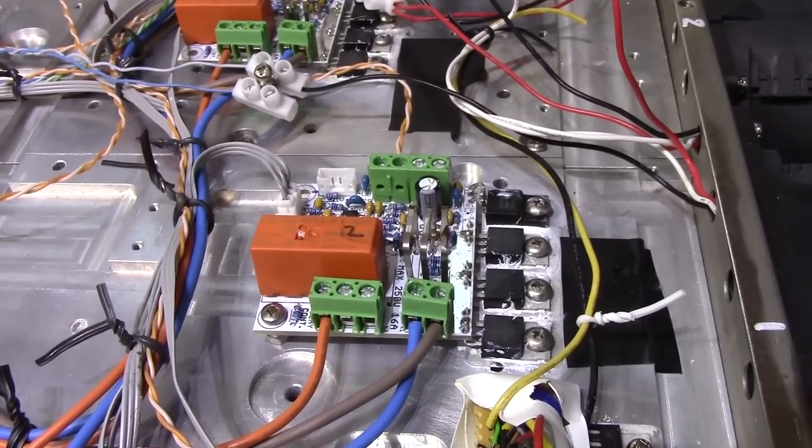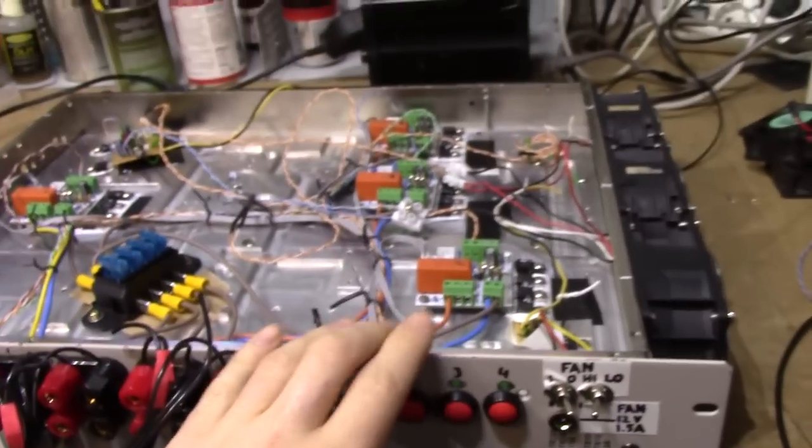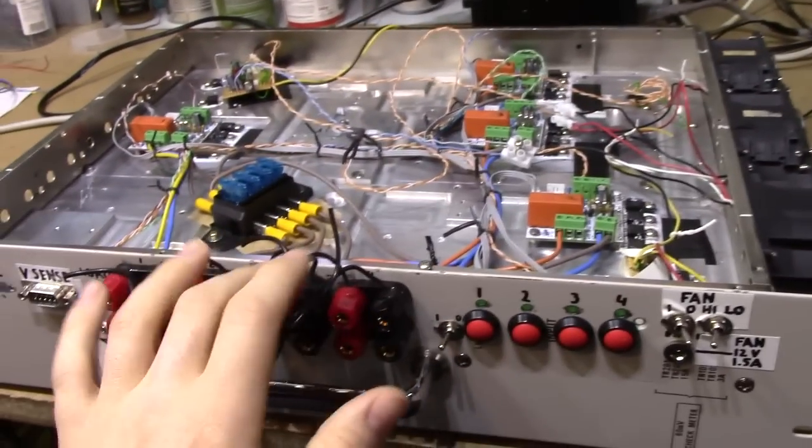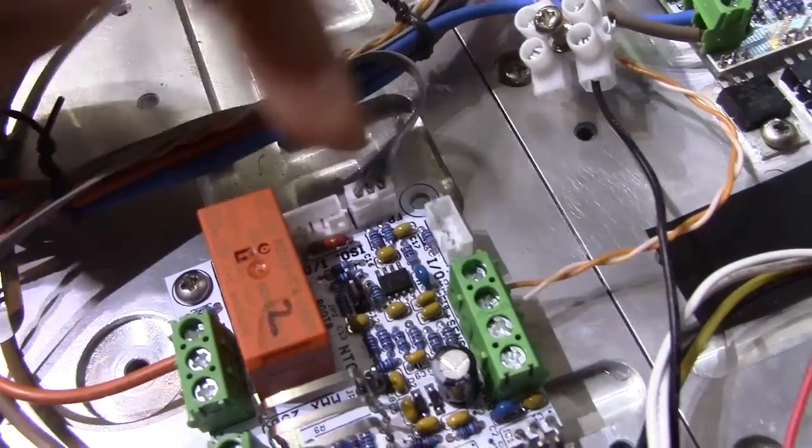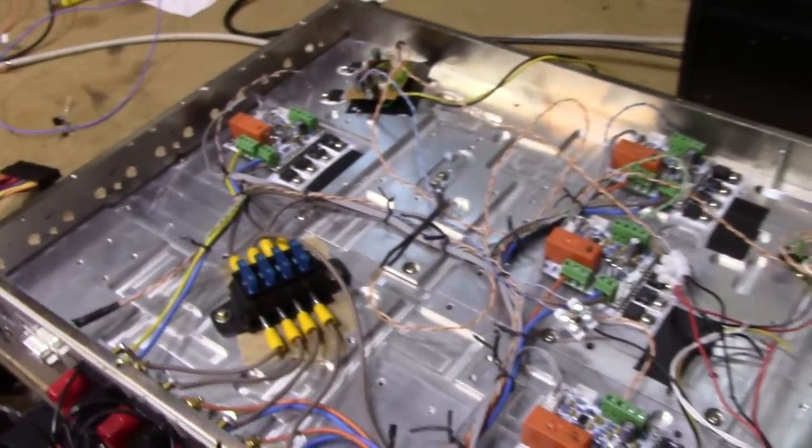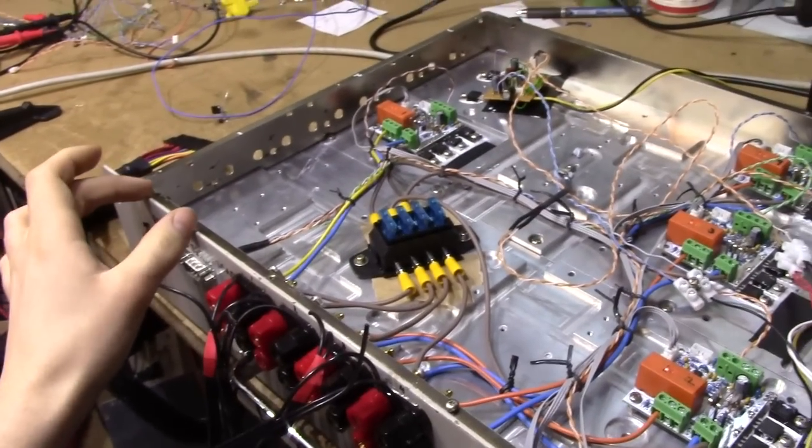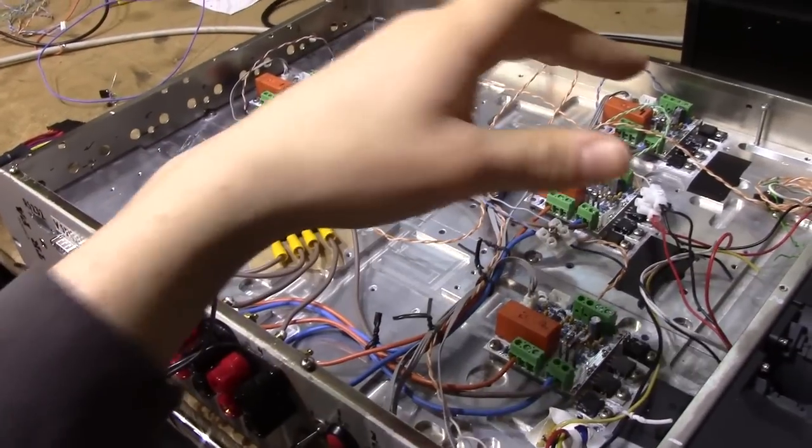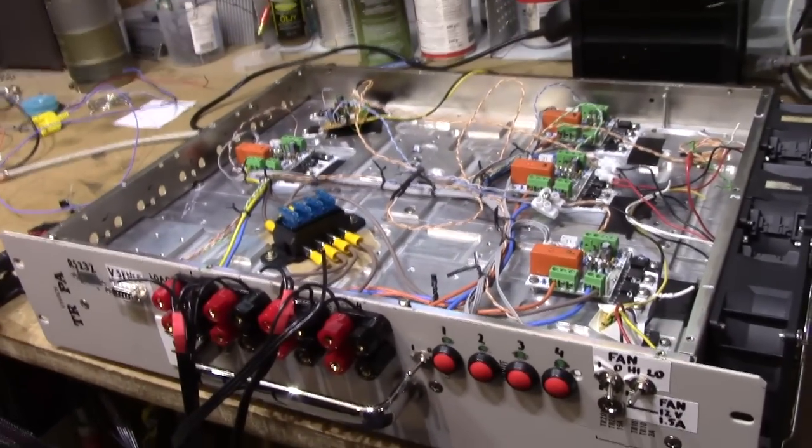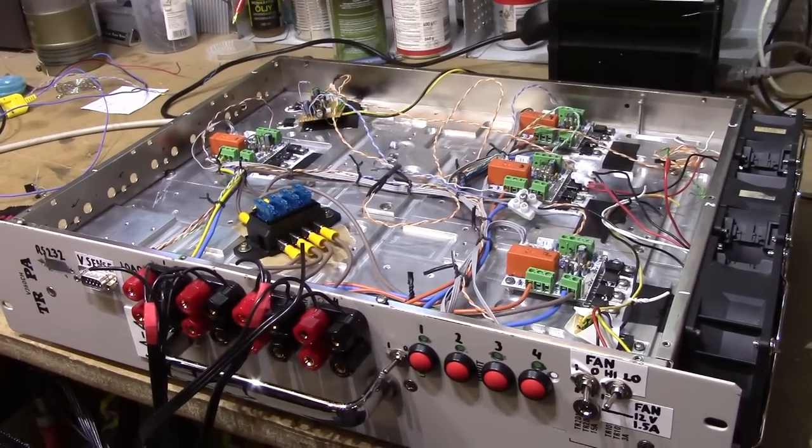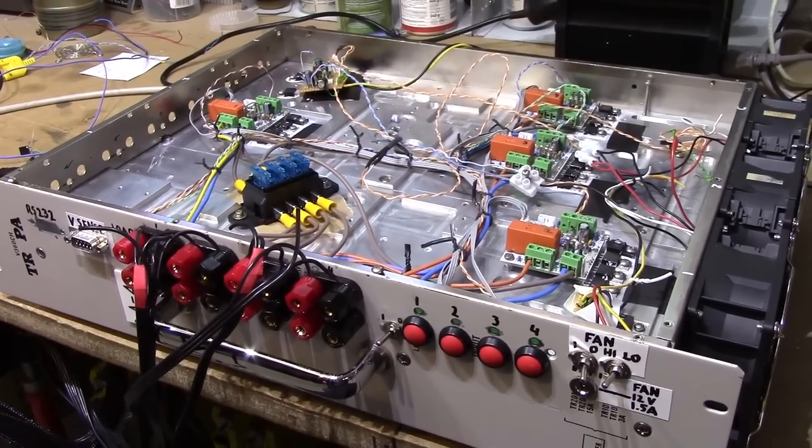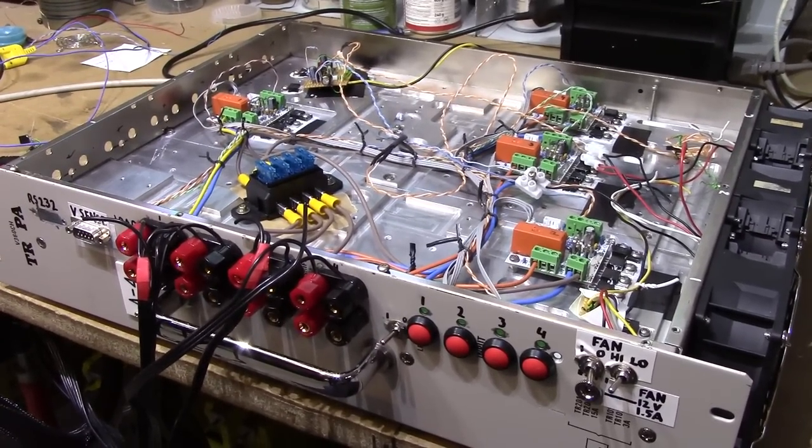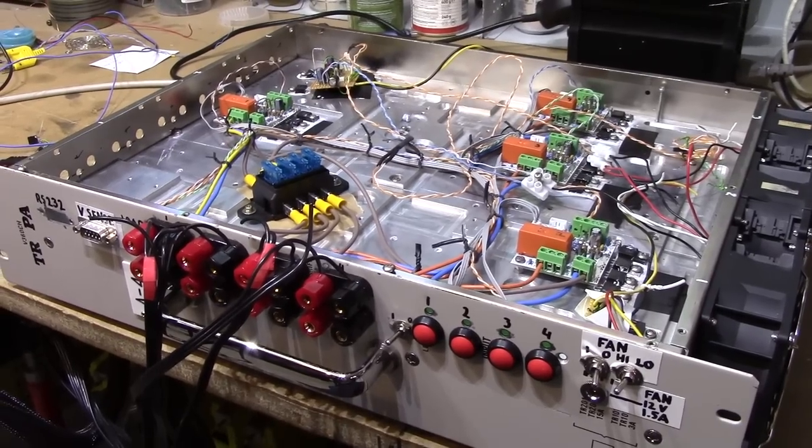They are also electrically isolated from each other, so there's no connection between the heatsink and the boards or the output terminals between the boards. They've got isolated serial ports as well as unisolated serial ports, which enables them to essentially daisy chain together. This is in order to be able to test 48V banks, since you can't just put current sinks in series. That's very difficult to implement compared to just having them isolated.